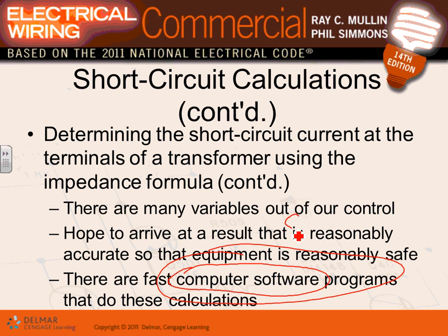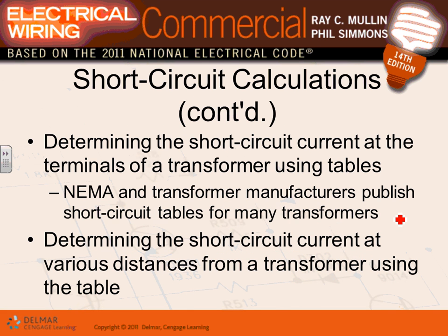So a lot of variables, and because of all these variables, I want to emphasize that we will use software like SKM PTW, so we can arrive at a value that we feel comfortable about. You know what I mean? Instead of doing it by hand, you might not find a chart for every single scenario, every single conduit, every single transformer. Software, like you've seen, Brian, has thousands of components in its library that you can pull from. Every manufacturer of every transformer has data about their transformer in the software. So your chances of arriving at a number close to the truth are much higher.